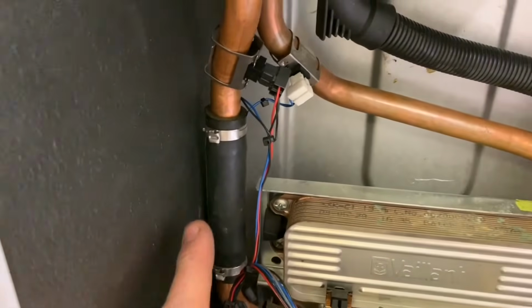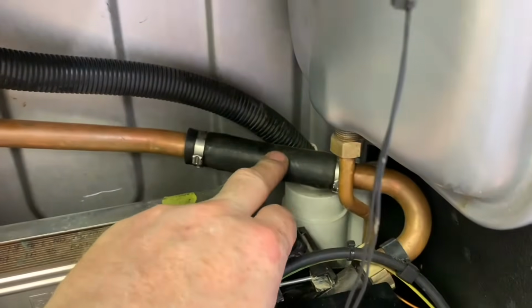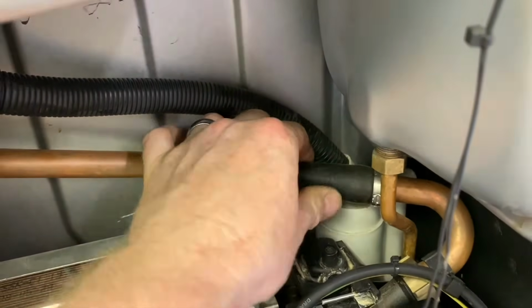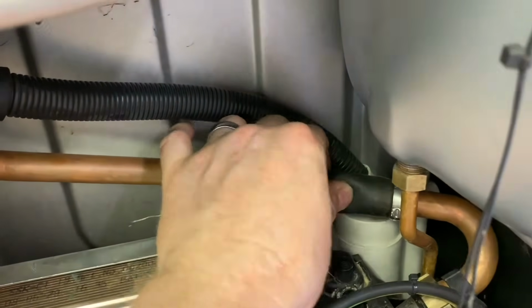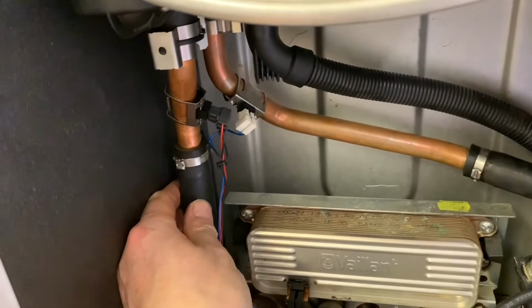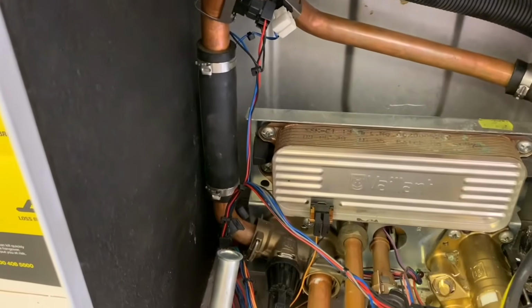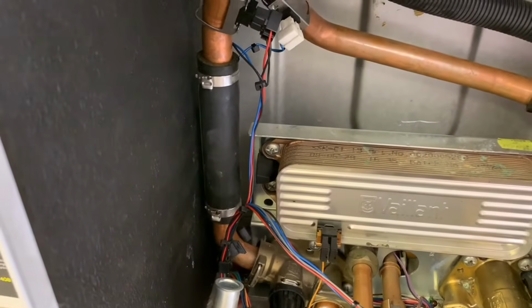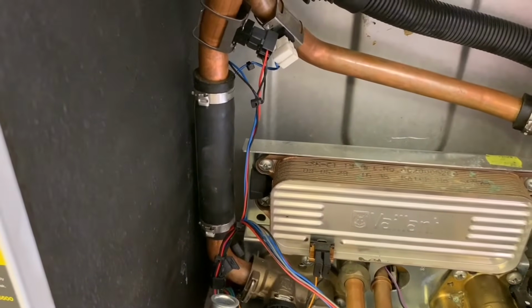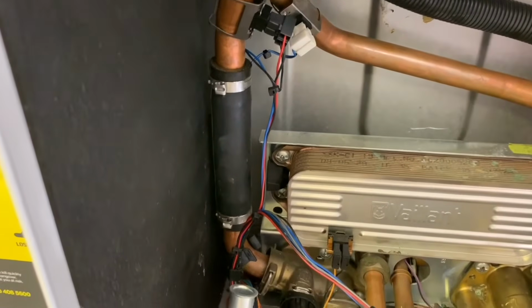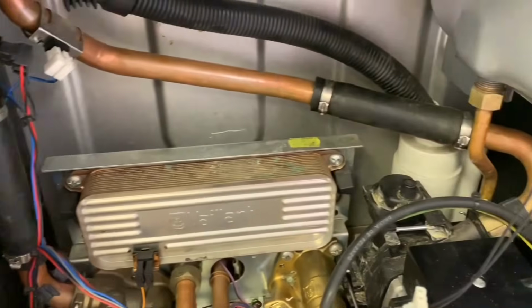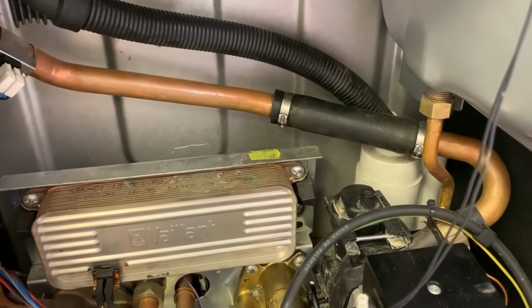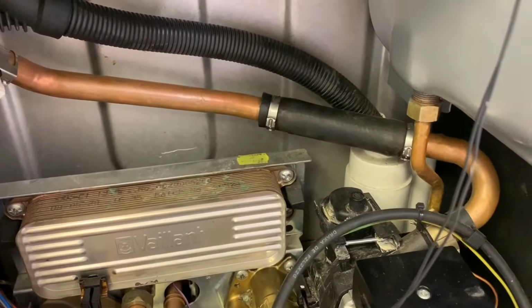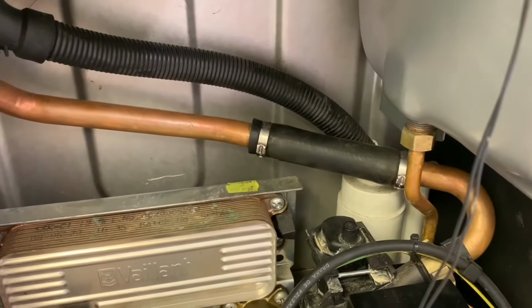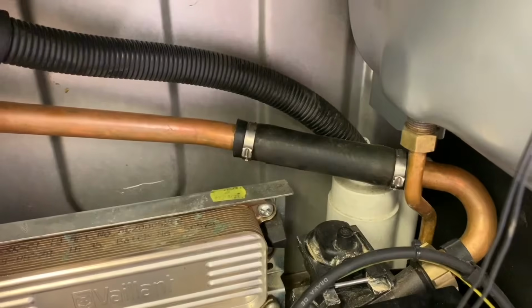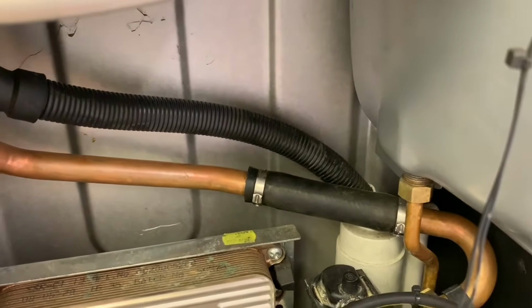So you can see there are two rubbers. There's one here on the flow and this one's on the return. Now there's no water in this, but it's quite flexible, these. They're not rock hard. Now they would be rock hard. They need changing. They're useless. They were put in originally to help with sound reduction when the water's flowing through, but have just become a massive big pain and leak constantly and split. So you've always got to change them. If they're fine and the customer doesn't want them changing, they don't have to, but you would always advise your customer to make sure that they get checked and changed.